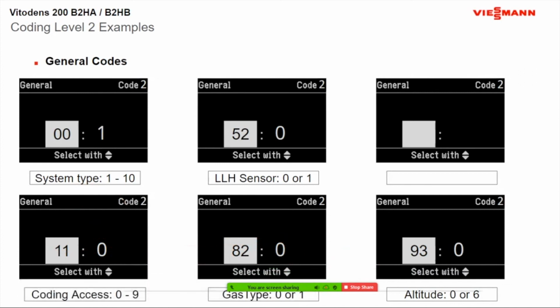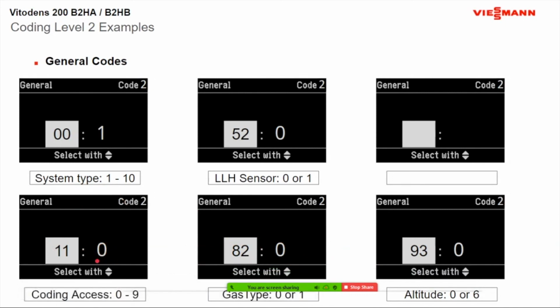So it's kind of like a lock. Otherwise, homeowners could go up to 82 and change it from natural gas to propane by messing it up. So it's a kind of safety on there. The other thing too is a lot of times when you put that 9 in there, I used to get the phone call: I put the 9 in there, but it's switched back to a 0. It's going to do that. It's going to switch back to a 0.